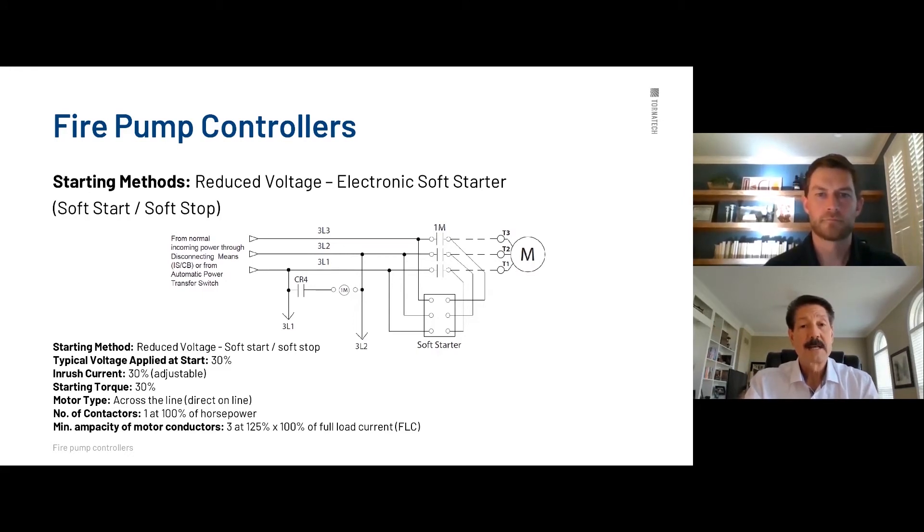Oh, soft start. Here we are. This is that little black box I'm talking about. Again, don't just, don't get confused thinking a soft start is like a VFD, a variable frequency drive because it is, it is alike because they're both electronic, but there is differences. So a soft start will allow you to ramp up the amount, your motor up to a certain speed. Now we all know on normal power by code, you need to have your motor up and running in 10 seconds or less. That's the maximum amount by code. So a soft start will allow you to do two things. You could ramp that speed up a little quicker if you want, or you could, you know, it's feel adjusted, feel adjustable, but it's factory set for the optimum ramp up time for that particular horsepower size motor. You could ramp down and have a slow ramp down in cases of that too. I mean, you can go both ways.